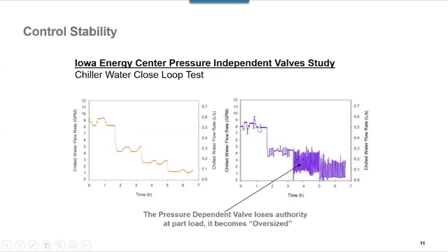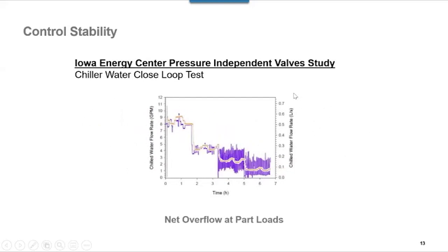Not too bad at heavier loads, but when we get into that part load condition, 50% and under, now we just start oscillating and hunting back and forth, due in fact to the valve losing its authority at part load, and it's becoming an oversized control valve. So in this case, our overflow is basically a net overflow at part loads.